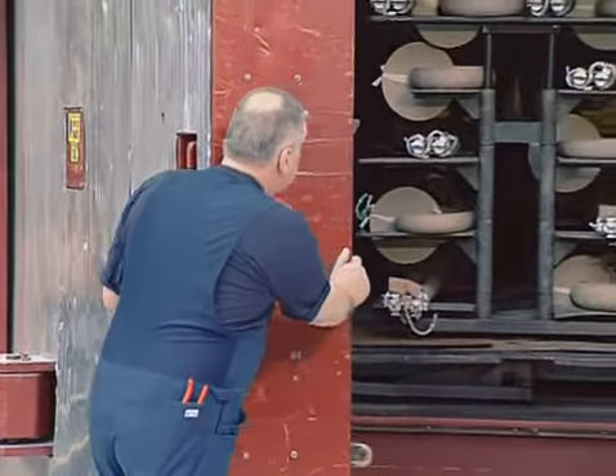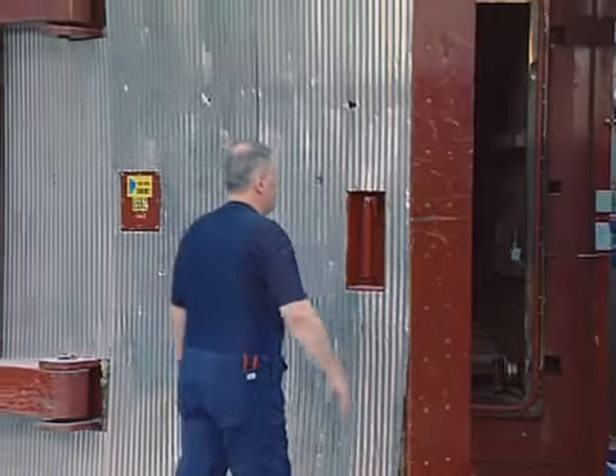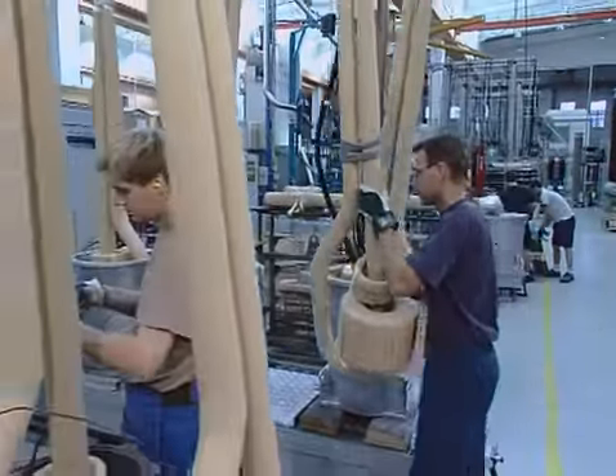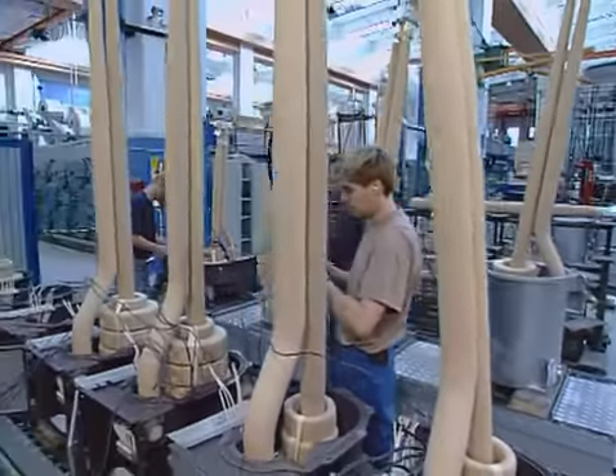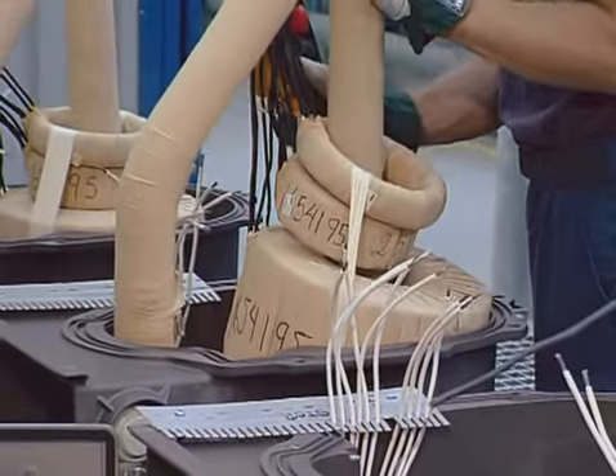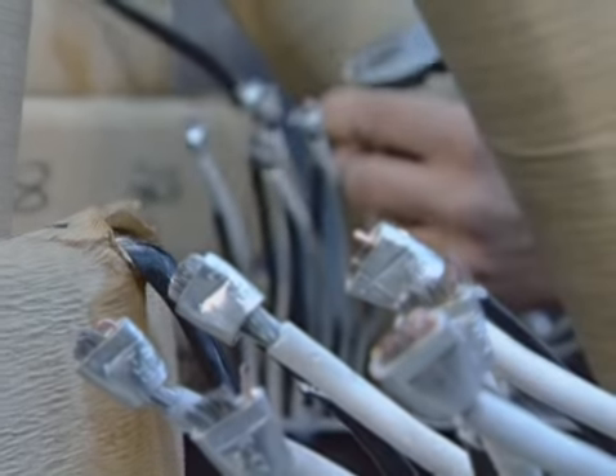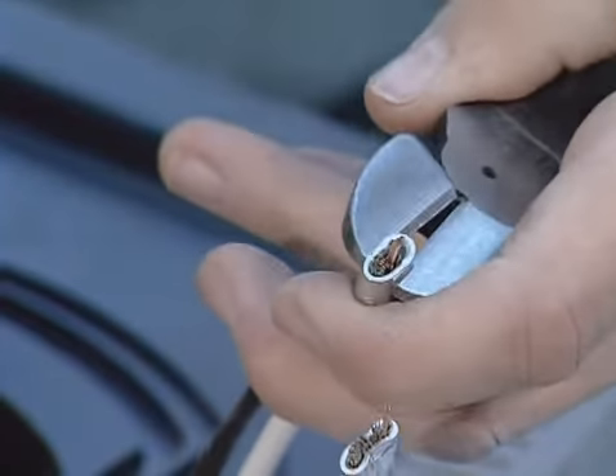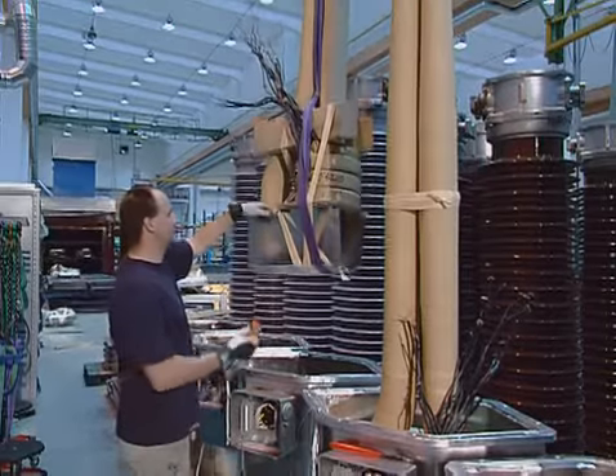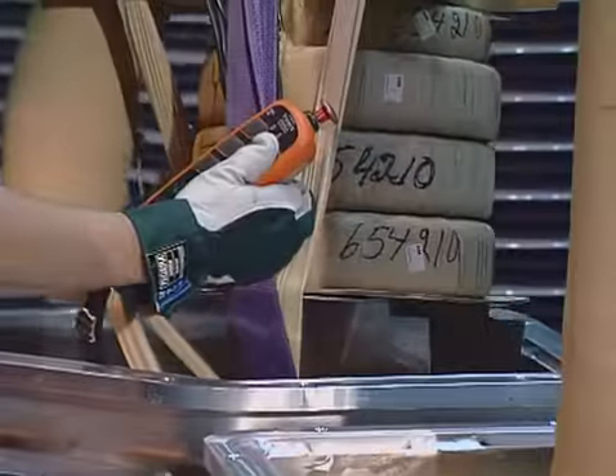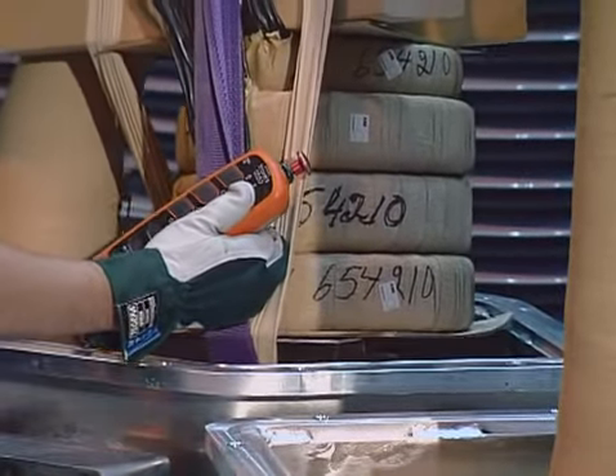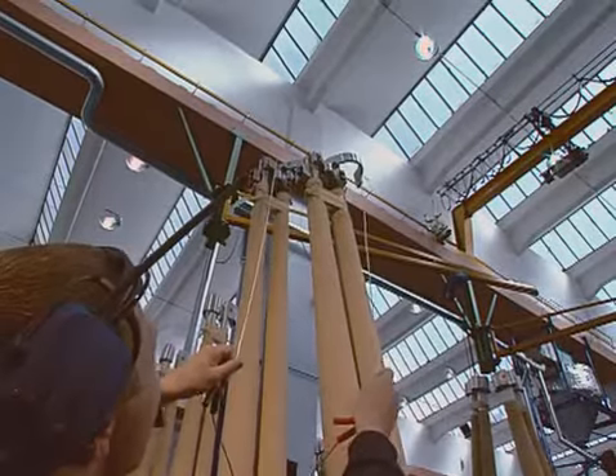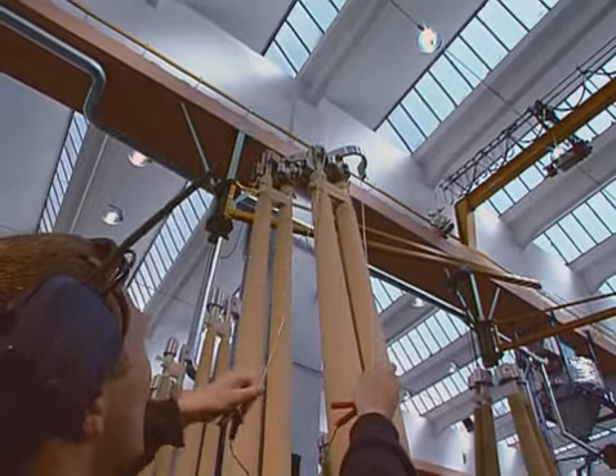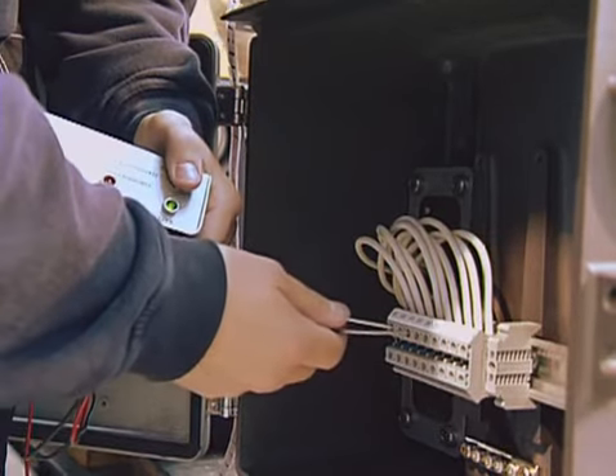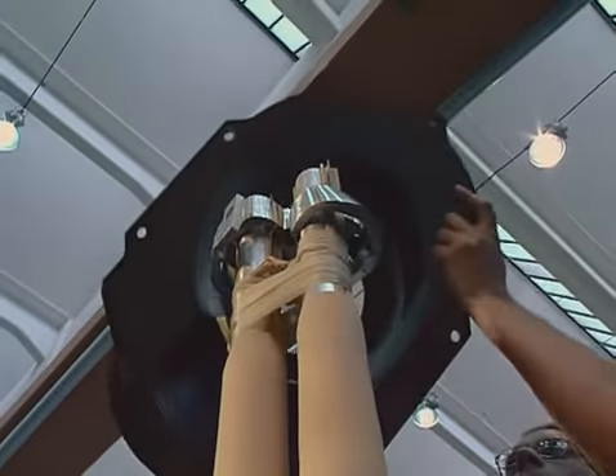The active part is then dried in an oven while in a vacuum. After drying, the active part is lowered into its tank, and then all the terminals are connected. Current transformers are always built according to the principal design, irrespective of their size. All of the connections are checked in order to ensure their function. After this is carried out, the upper part of the tank is assembled.